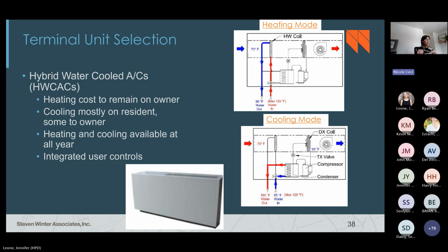And it does it on a two-pipe system, when we have that hydronic loop operating in the temperature ranges that I established in the earlier slides. So this approach keeps our heating cost on the house, very little power for the terminal units. And because we are using that water source heat pump section to run cooling, most of the cooling cost remains on the terminal unit. These are also console units. They have onboard controls, so no integration required there.